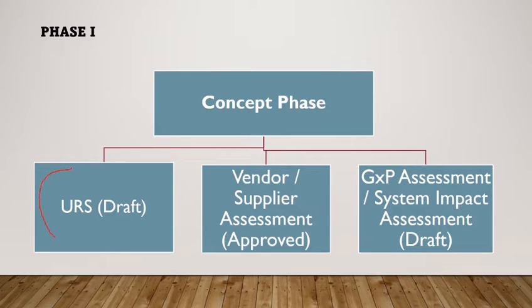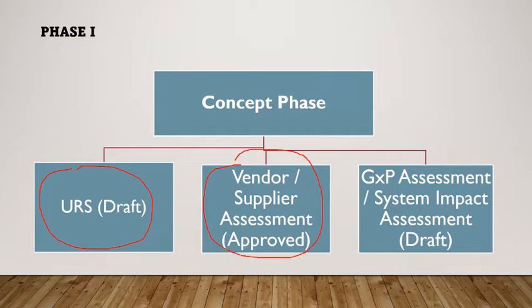First, we need to prepare the user requirement specification in draft mode. Basically, the URS defines the business processes — that is end user requirements, operational requirements and regulatory requirements. All these requirements must be testable and verifiable. Further, we need to perform the vendor or supplier assessment to evaluate the maturity of the vendor and product. The vendor must follow regulatory compliance, and we need to evaluate the vendor quality management system, length of time in the market, product complexity and after-market services. This document must be approved before moving on to the next deliverables.